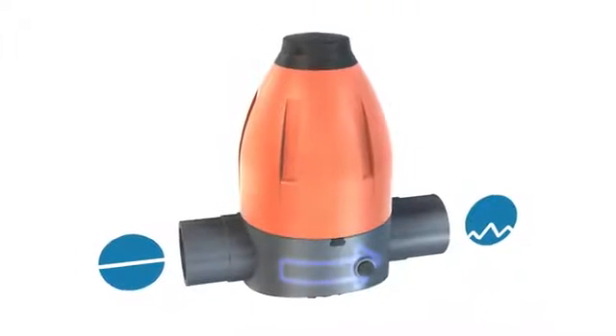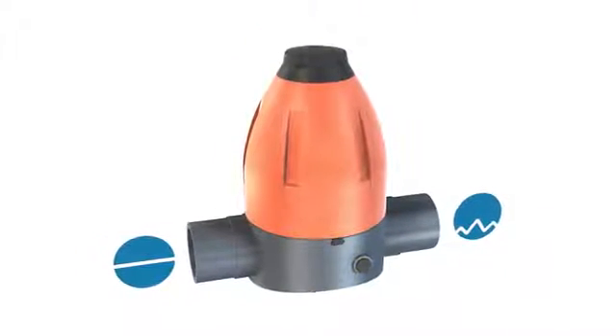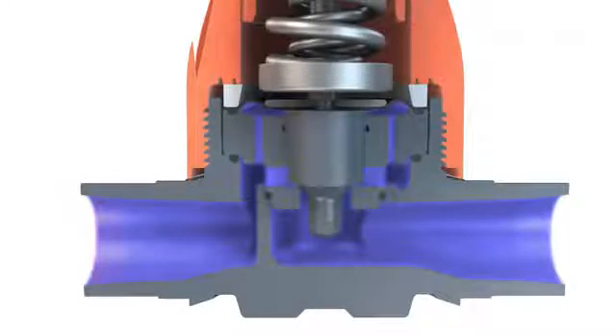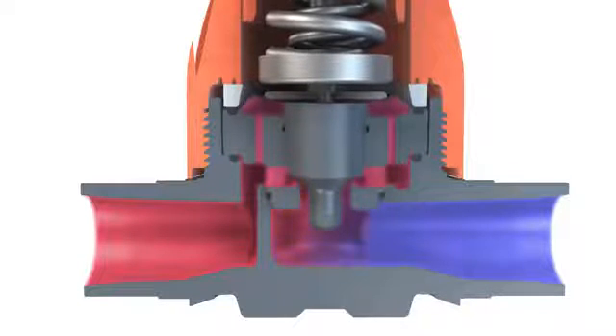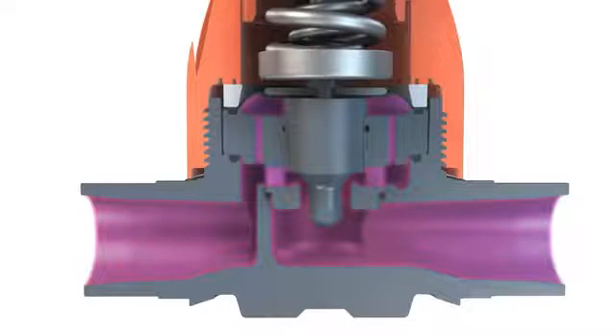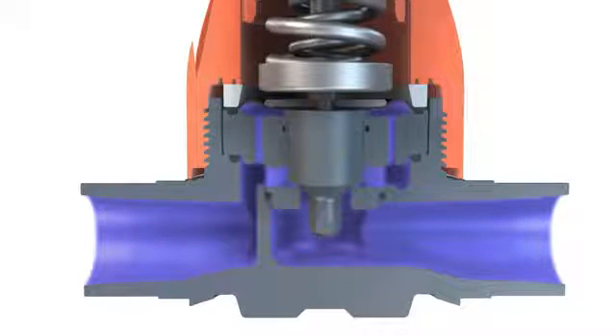Constant system pressure is no problem with the type 586 retaining valve. If the input pressure exceeds the set pressure, the medium is diverted over the bore channels to the diaphragm, which it presses upwards together with the piston. The valve opens and the pressure is vented.